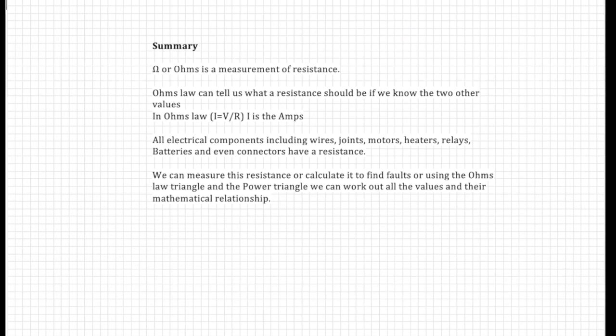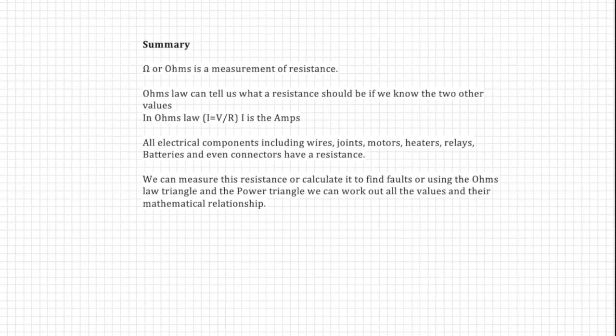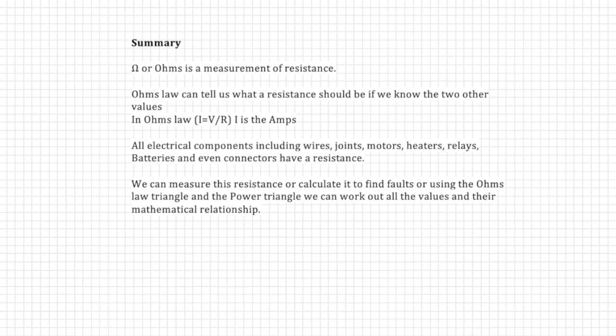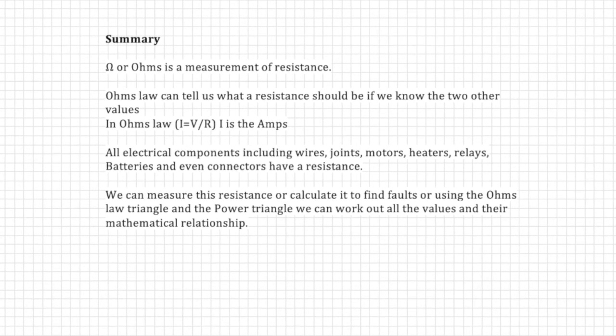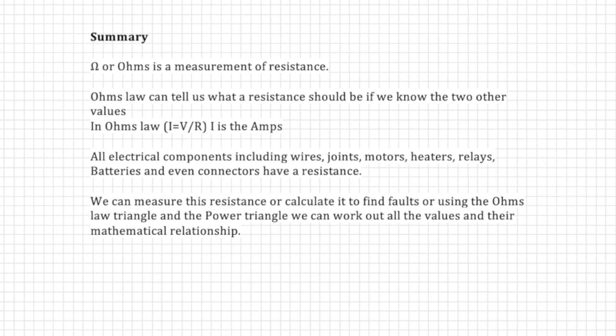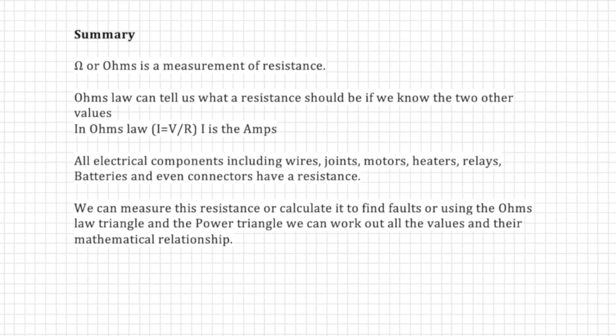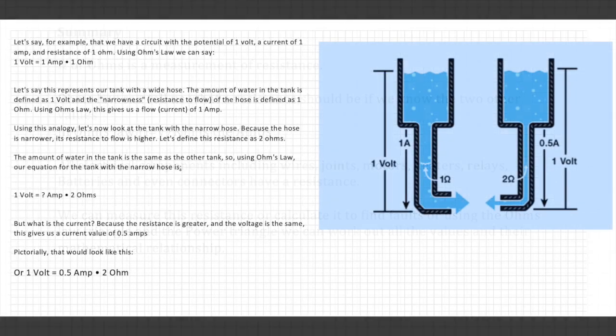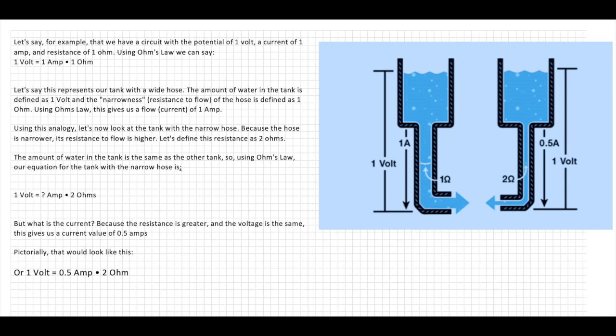Ohm's law can tell us what a resistance should be if we know two of the other values. Ohm's law is I equals V over R, where I is amps. All electrical components including wires, joints, motors, heaters, relays, batteries, and even connectors have a resistance. Ohm's law is fundamental to fault finding.